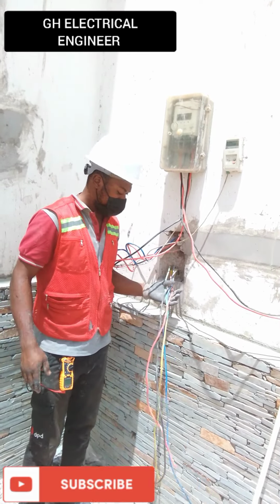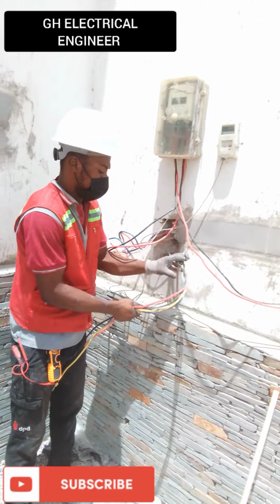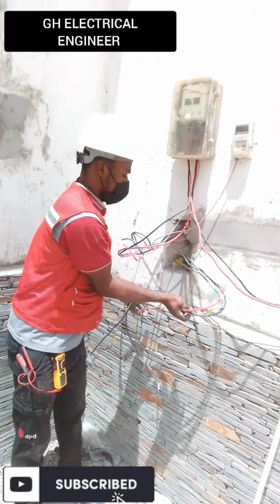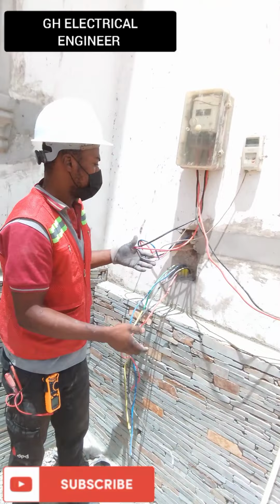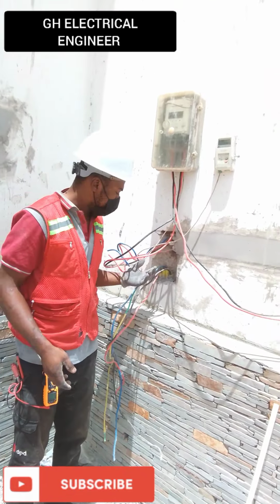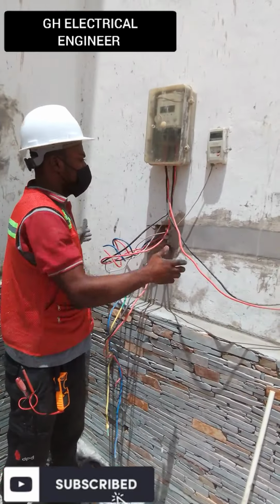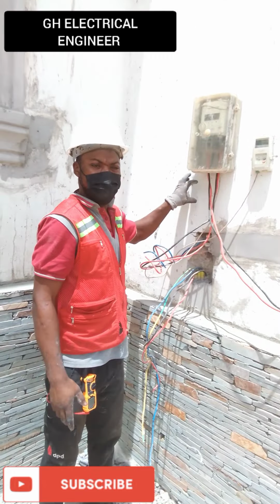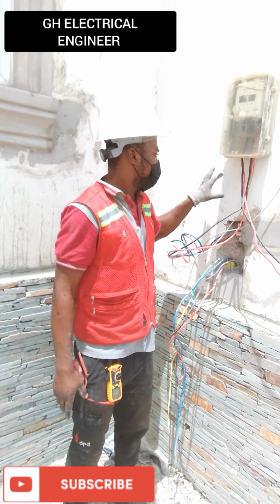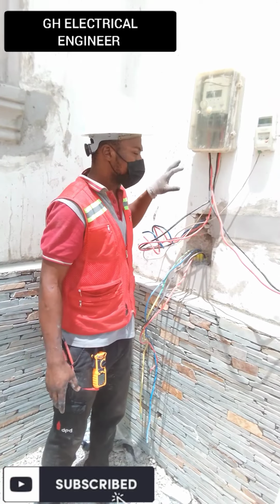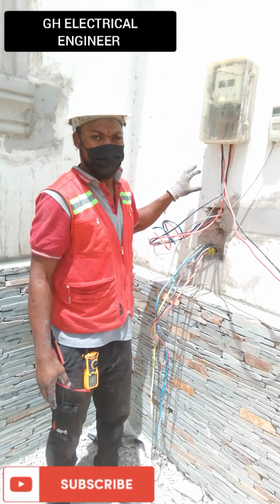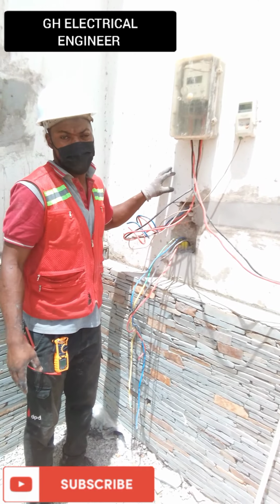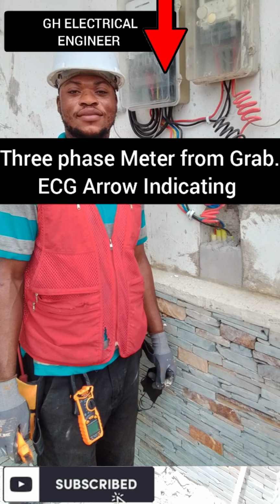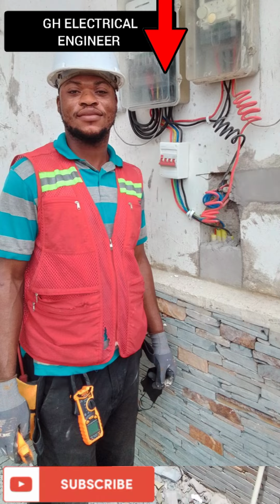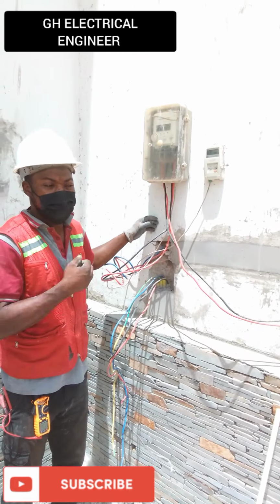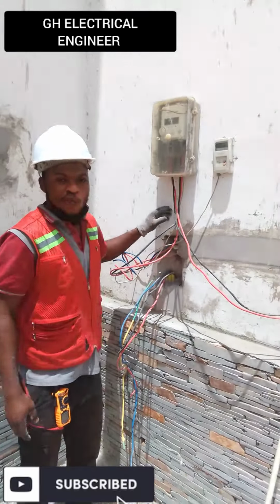So in here, you can see this cable. This cable goes all the way to the automatic changeover. And this cable doesn't have to go directly to the meter, as the old electrician has done. We have to put the MCB to protect the cable going through the automatic changeover. We have to use the MCB, especially 100 amps. You can see that is where they install the meter, and you can see we have already put the MCB there.